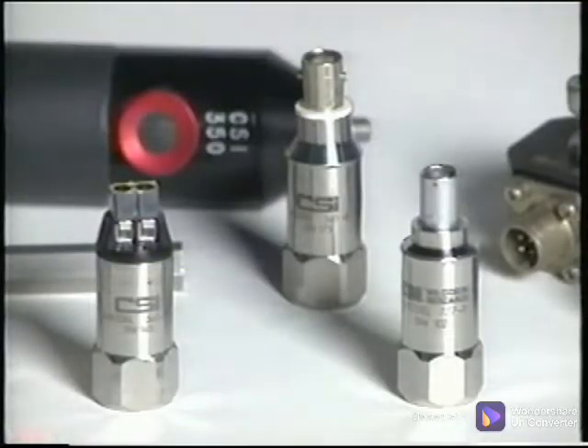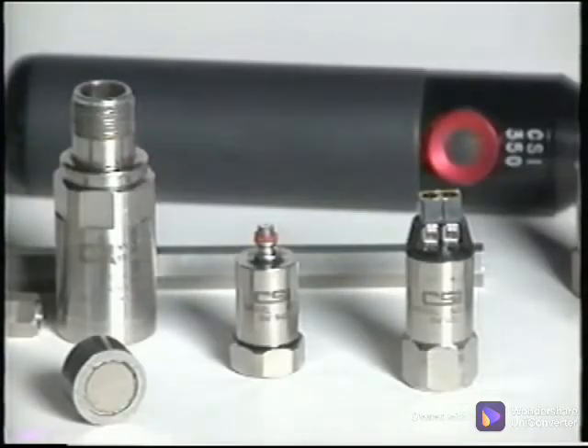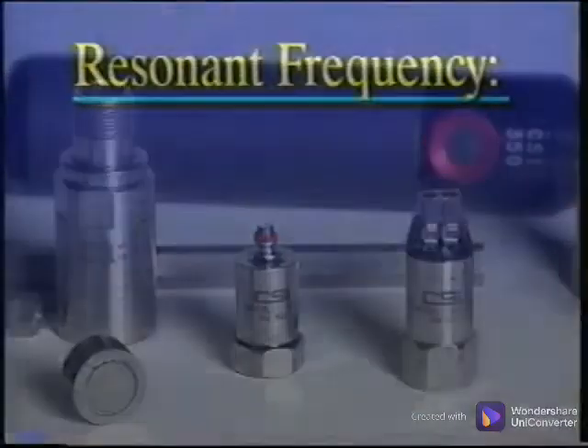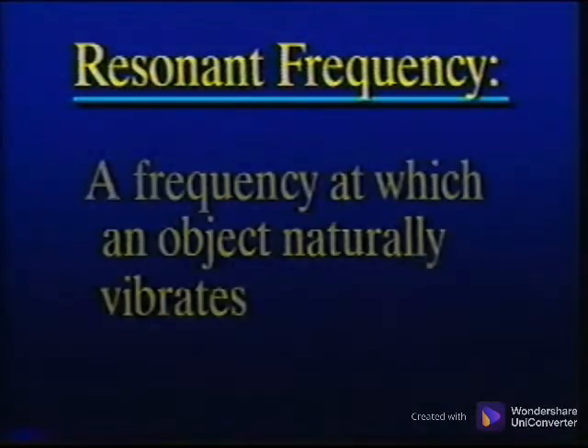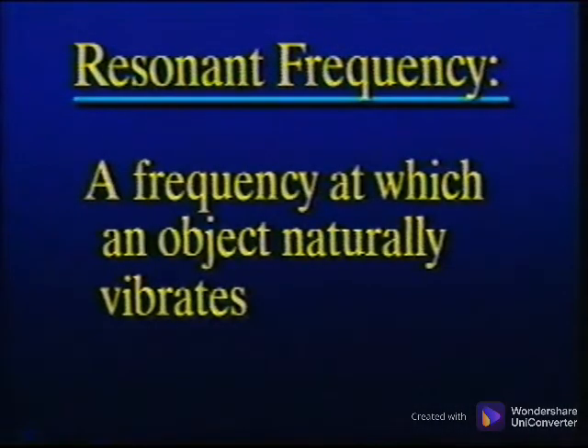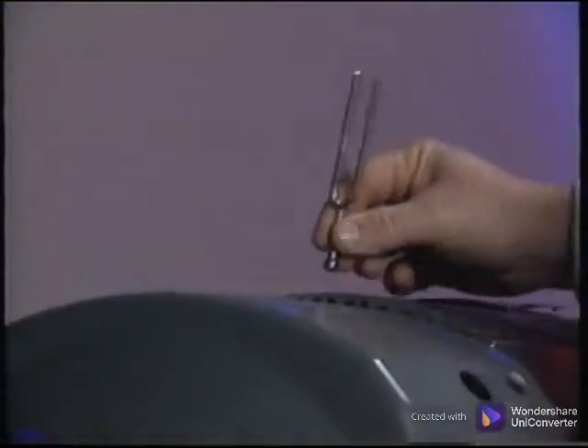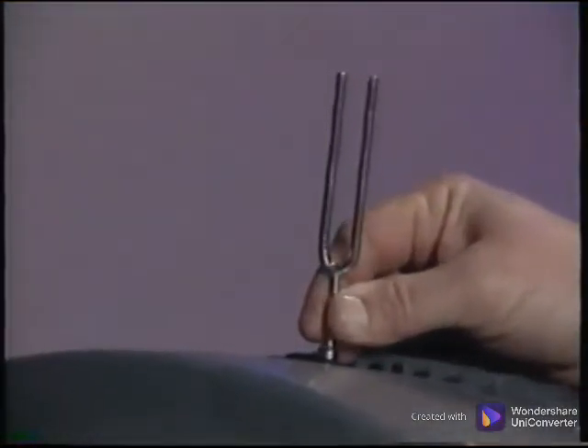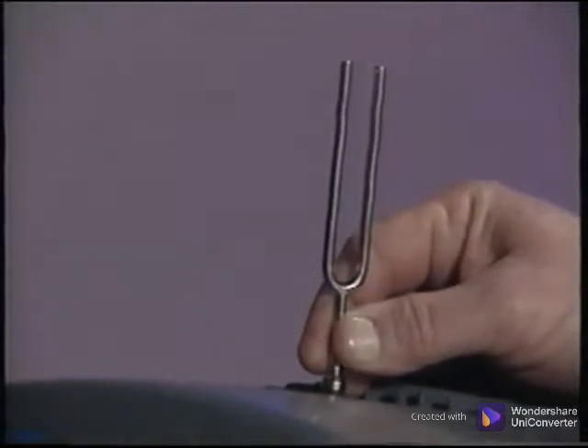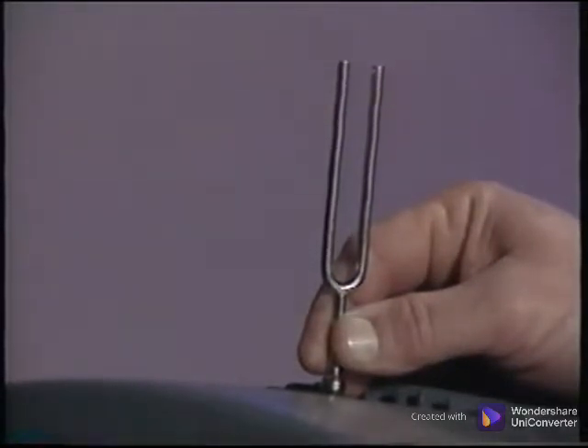Although a sensor is designed to perform well within its stated frequency ranges, there are resonant frequencies unique to the method of mounting the sensor that greatly affect its linear response range. A resonant frequency is a frequency that an object likes to vibrate at. Every object has at least one resonant frequency. When this tuning fork is struck, it will vibrate at a frequency that is dictated by its design.